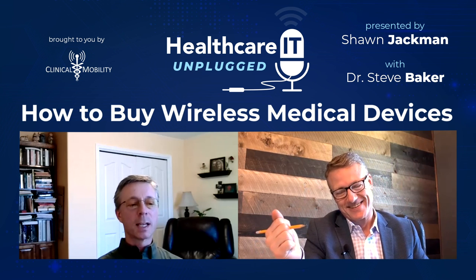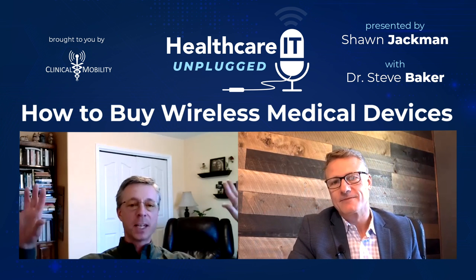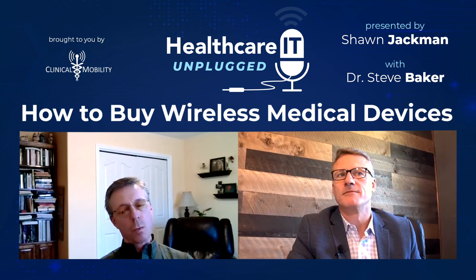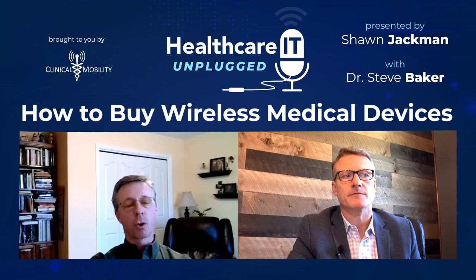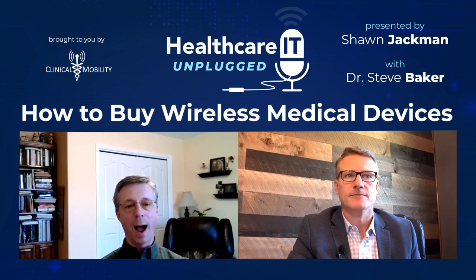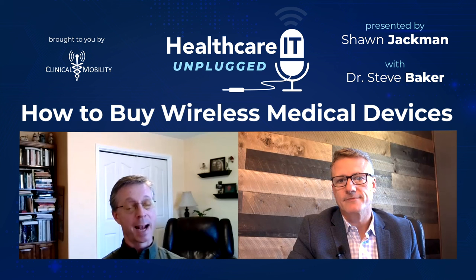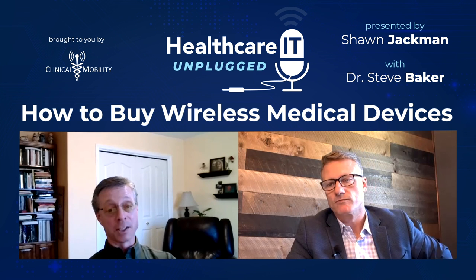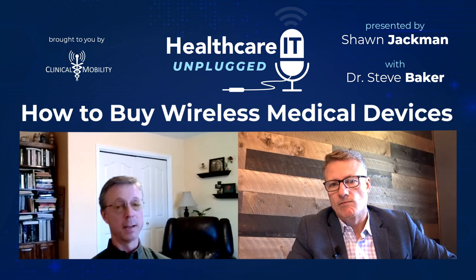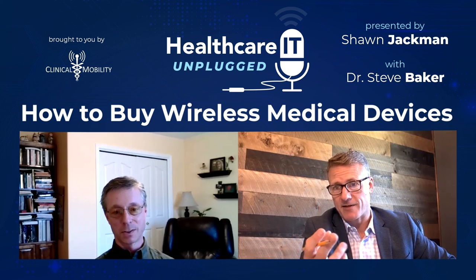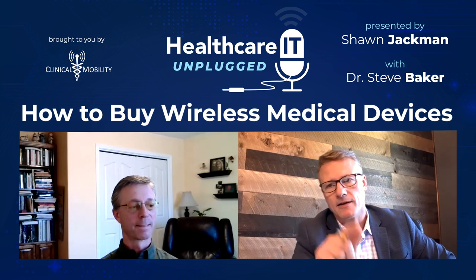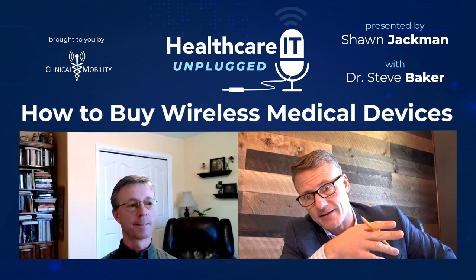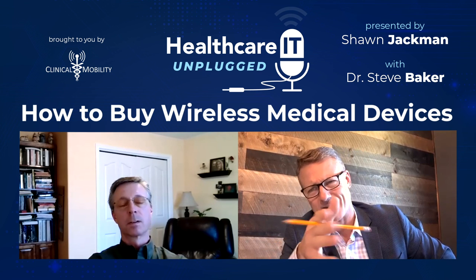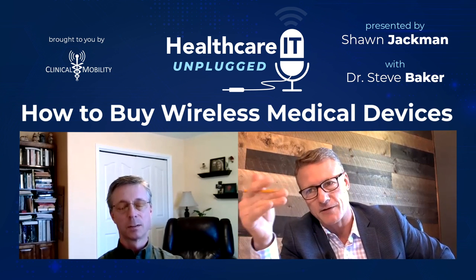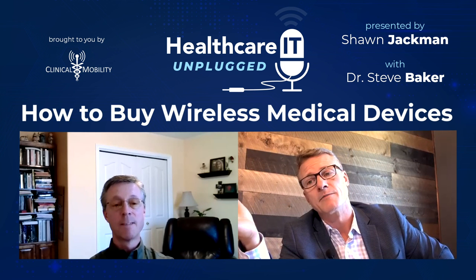So getting back to the part about when medical device manufacturers say the FDA won't let me - that's BS. More accurately, the FDA requires that I do testing before I release this. But there's no 'FDA won't let me.' Actually, the FDA says you must have a way to provide software updates to address issues. In fact, it's the opposite. We've heard for years, 'no, I can't update.' I was calling BS on these folks because I actually read it and said, wait, there's no part of this that says it can't be in scope. It's categorically false.